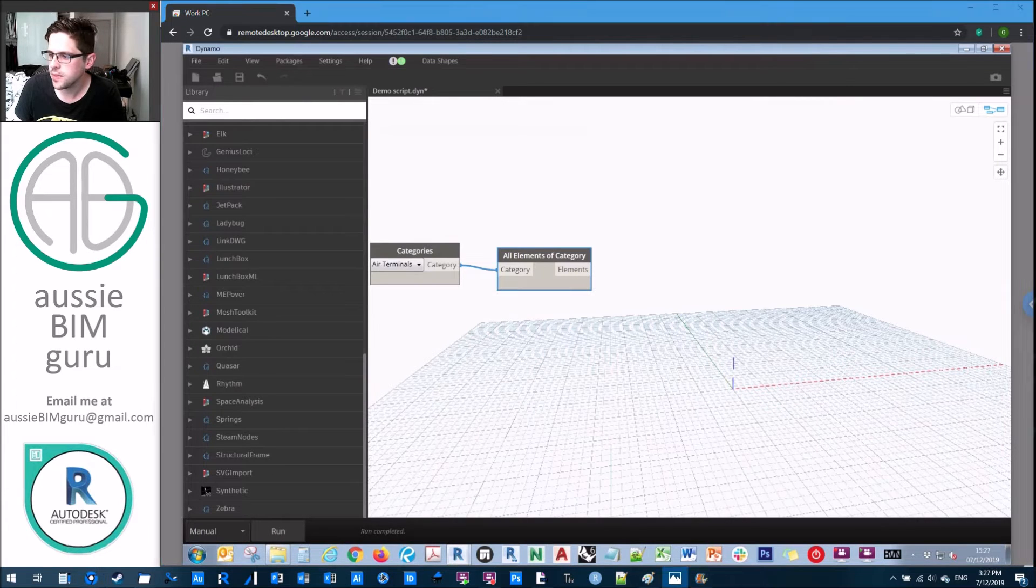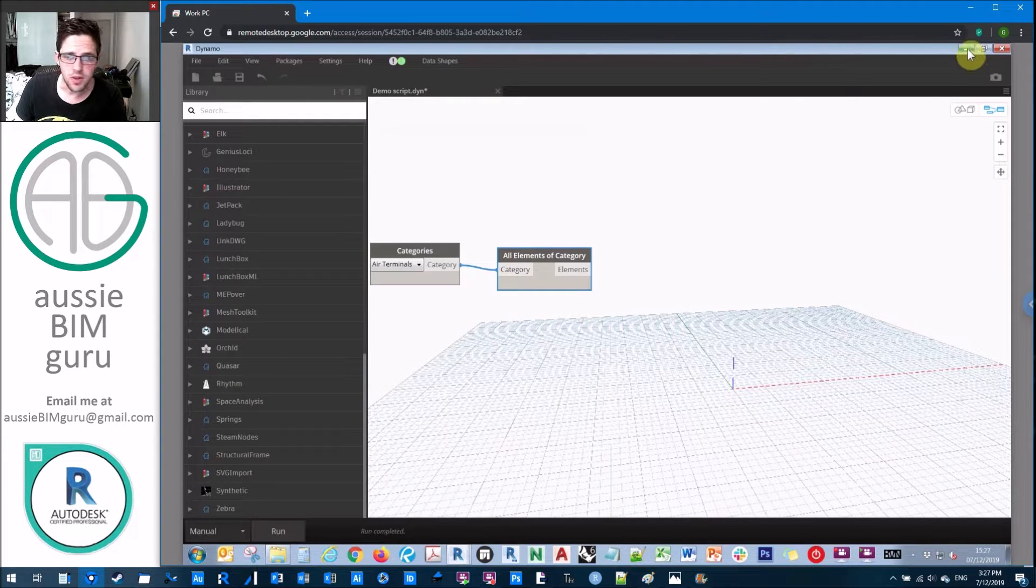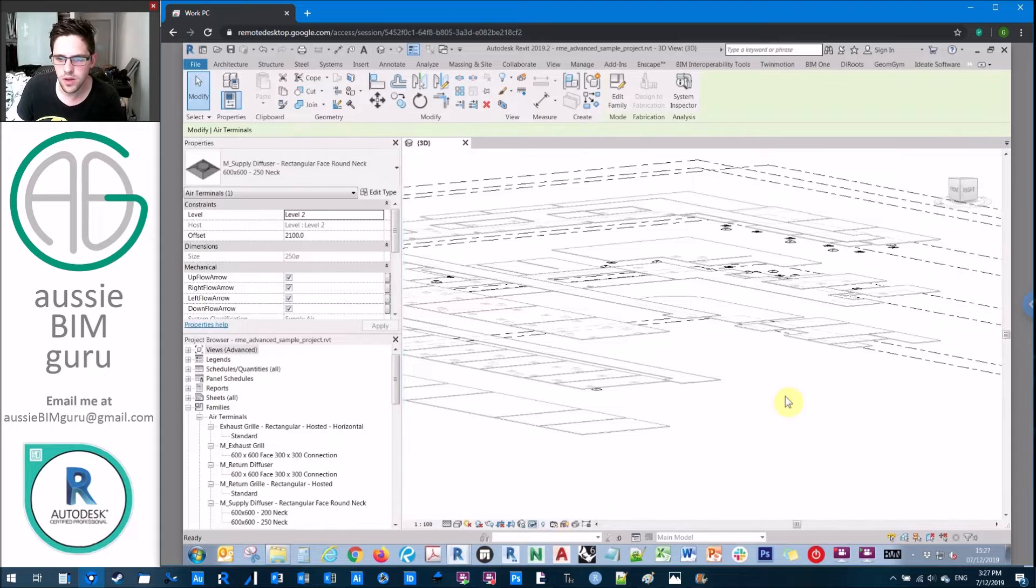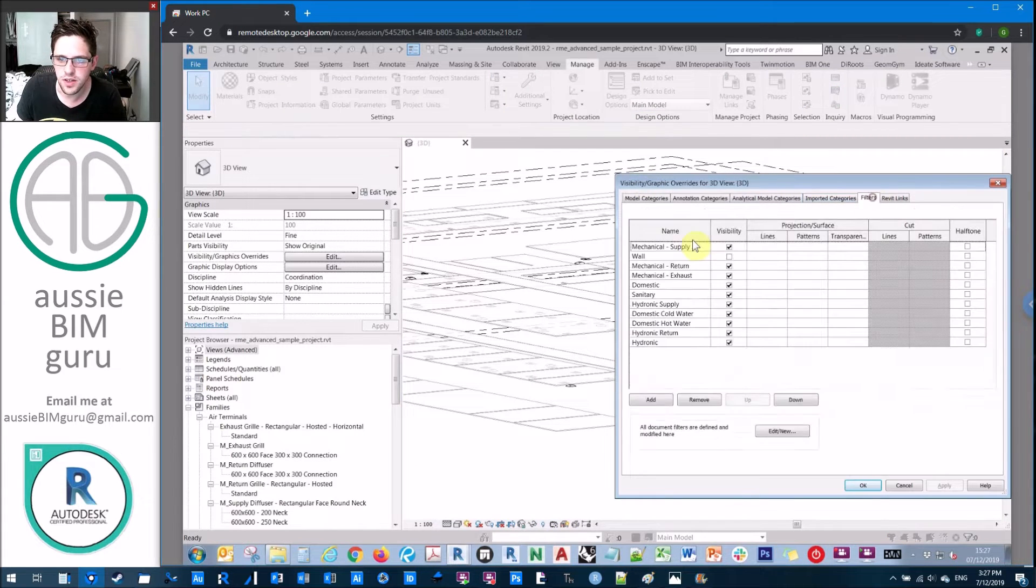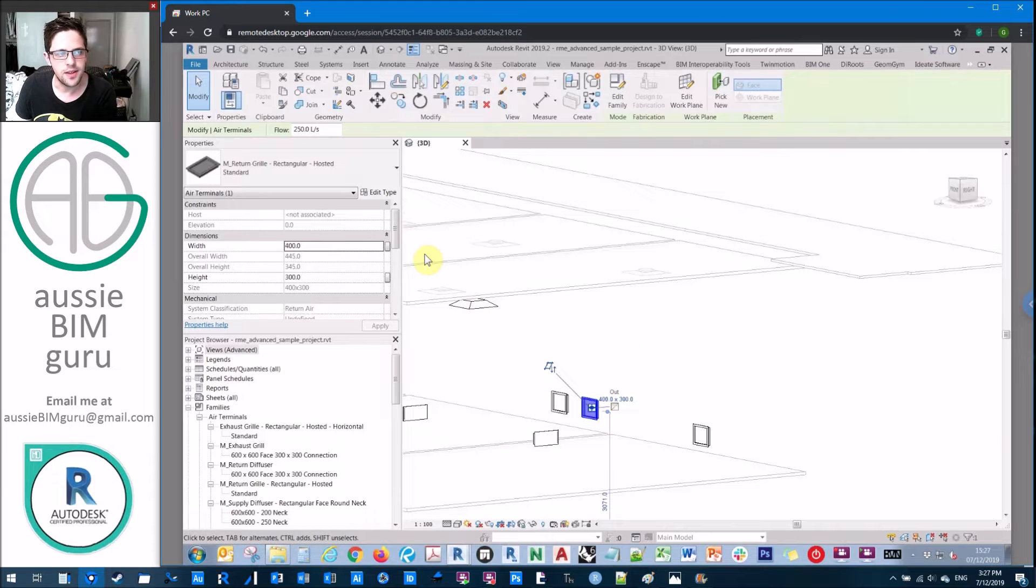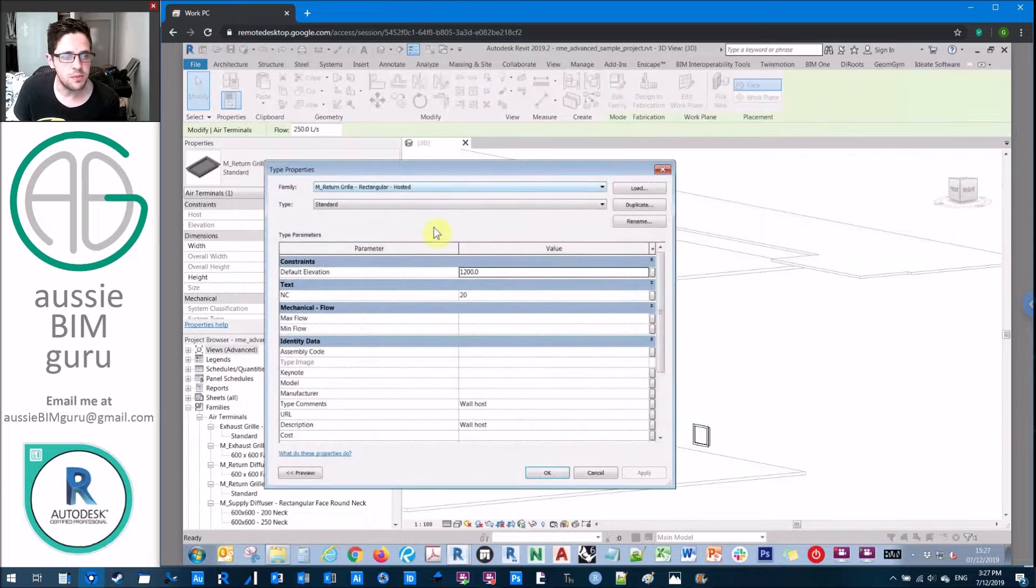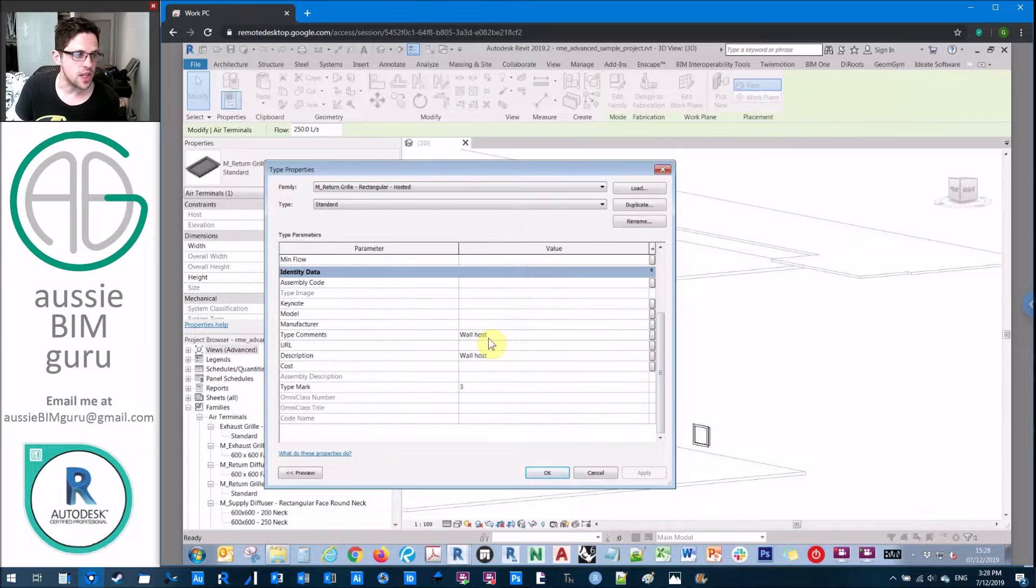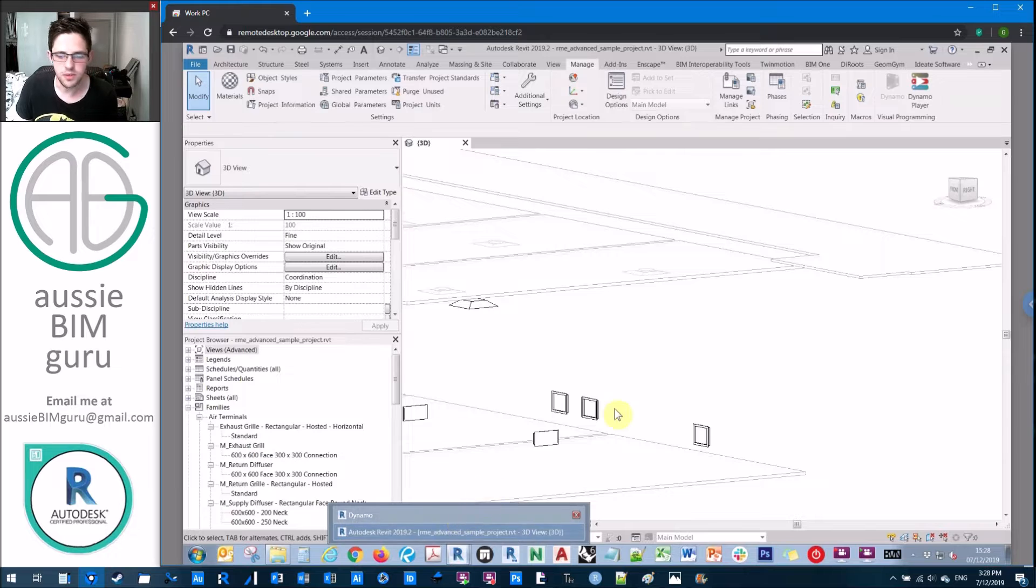Okay. So now we should get all of those as elements, which we do. We've got quite a lot of them in this case. It's important to note that I'm getting air terminals and not all of them belong to a ceiling. So that's quite important to point out. So if I just turn off my temporary hide isolate, and I believe I've got a filter on as well. I've set up a filter to hide all the wall-hosted grills. If I turn this back on, we actually have a lot of wall terminals like this that don't belong to a ceiling. So we need to find a way to filter them out of the terminals we're dealing with. Usually the way I recommend doing this is by inputting some data into your families. So in this case, I've added a type comment or a description to these particular types, telling them whether it's a wall or a ceiling host. That way we can just focus on our ceiling hosted elements.